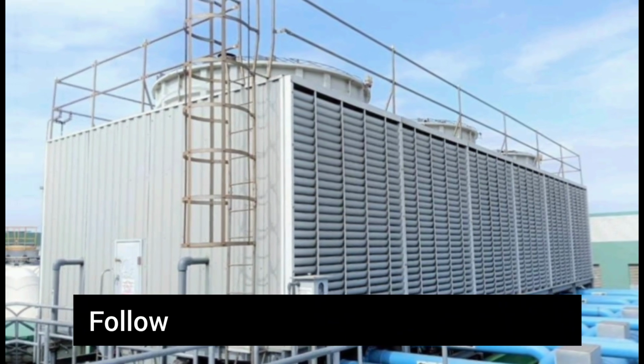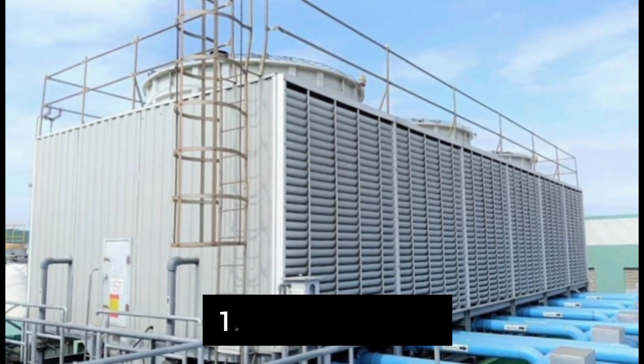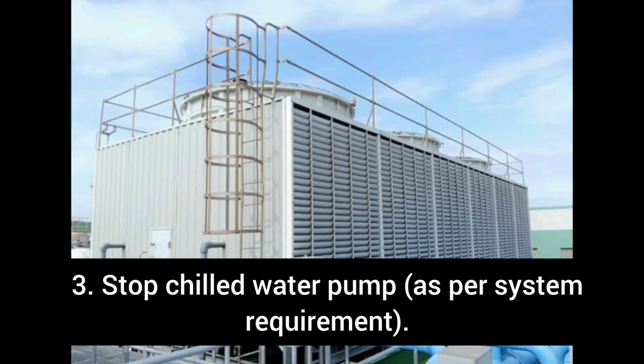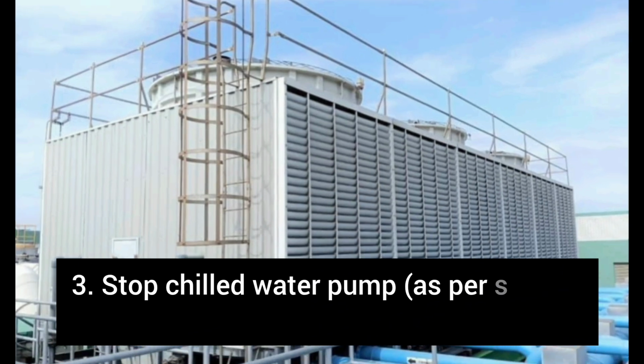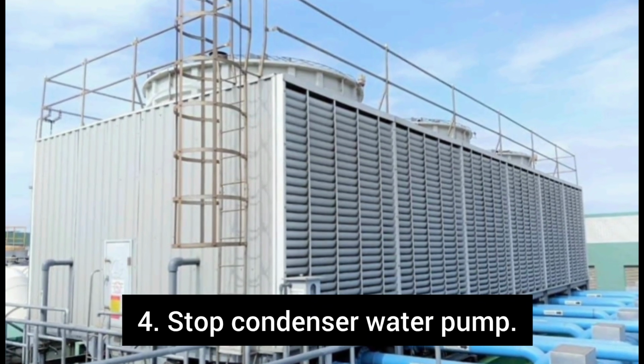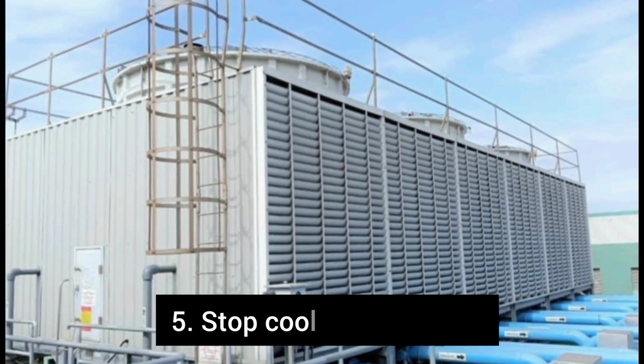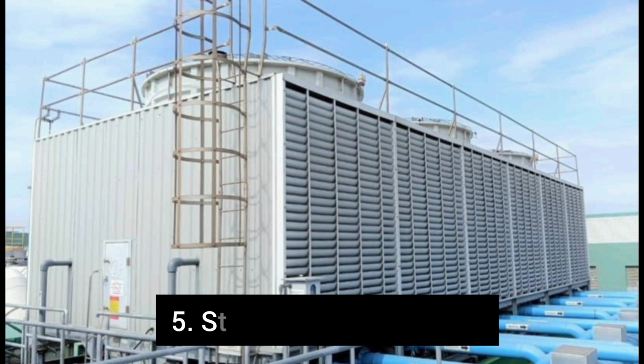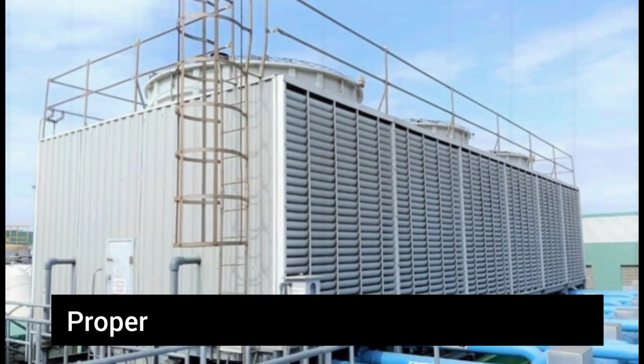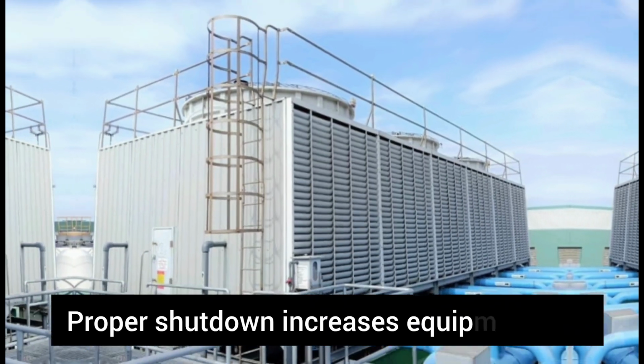Shutdown procedure. Follow the correct shutdown sequence. 1. Stop the chiller. 2. Wait for compressor shutdown. 3. Stop chilled water pump as per system requirement. 4. Stop condenser water pump. 5. Stop cooling tower fan. 6. Record operating data in the logbook. Proper shutdown increases equipment life.